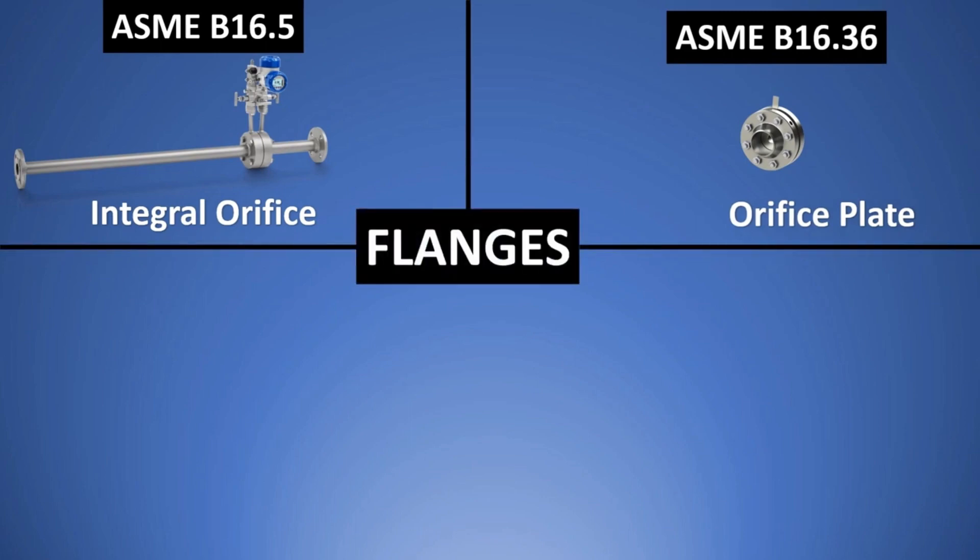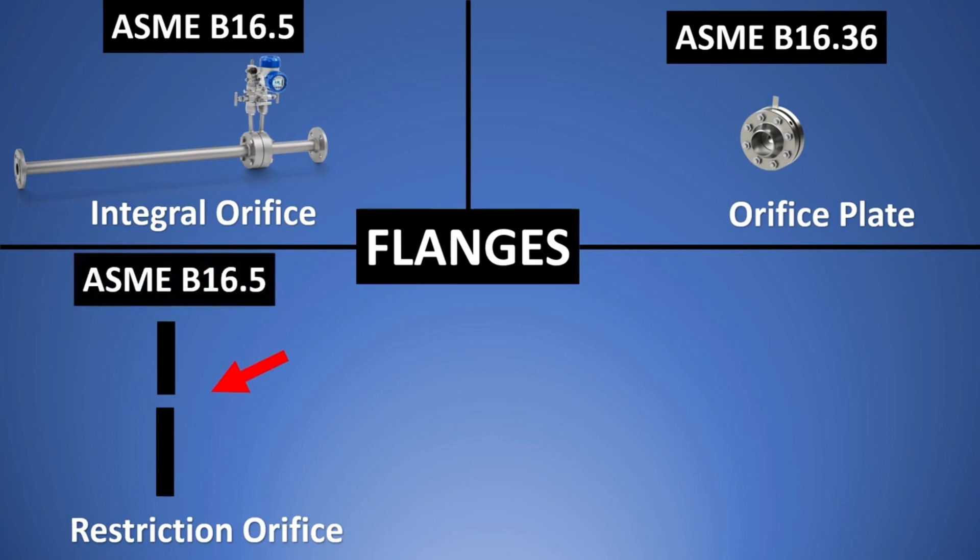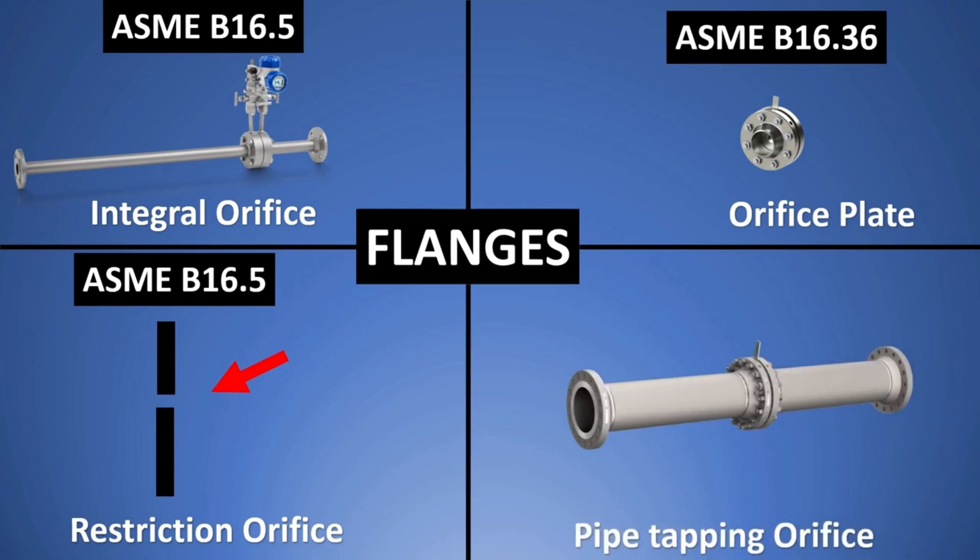Now if you tell me with this understanding for restriction orifice, what would you be using? Will you be using ASME 16.5 or 16.36? The answer is 16.5 because there are no holes drilled in the flanges. So you can use for restriction orifice ASME 16.5. Similarly, for pipe tappings, where tappings will be taken from pipe for very high line size orifice, you don't need any special standard for flanges. So you can go for ASME 16.5.